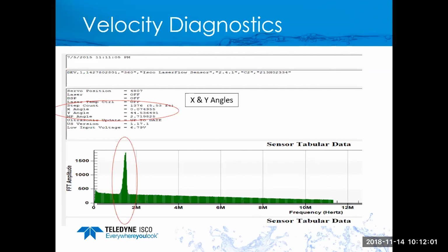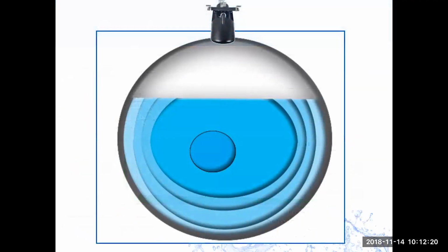So that tells me a couple things. The installation was nearly perfect. If the thing ever went underwater and became submerged and the water receded, this tells me that nothing moved. The laser mount held, and based on that signal, it tells me we don't have to go in and do anything. So you don't have to clean it, you don't have to touch it. So really, really good diagnostics information.